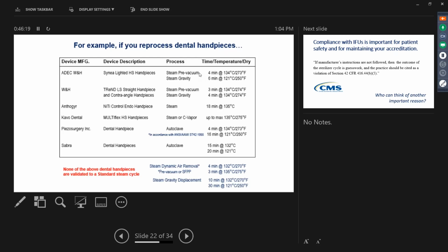Well, this one says it's a pre-vacuum or a gravity cycle, you have two choices. This one says the same thing, but their choices are different. This one doesn't say, it just says to steam it. And this one says you can steam it or chemical vapor it, but look, it's just stating temperature. So we have no idea. This one says autoclave it. And this one says according to AAMI ST42, which doesn't exist anymore.